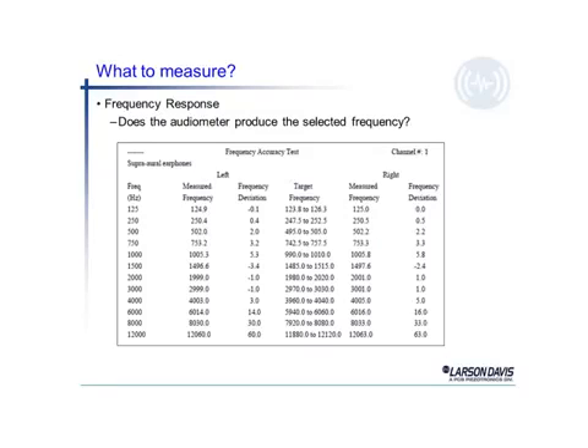We are also interested in the frequency response of the audiometer. If we take again an example here of 1000 hertz, we'll notice that we measured the audiometer at 1005 hertz. And 5 hertz seems like a fairly large deviation in today's standards. As we look at the target, we're allowed anywhere from 990 hertz up to 1010 hertz. And the audiometer is considered working properly, even with these larger deviations.